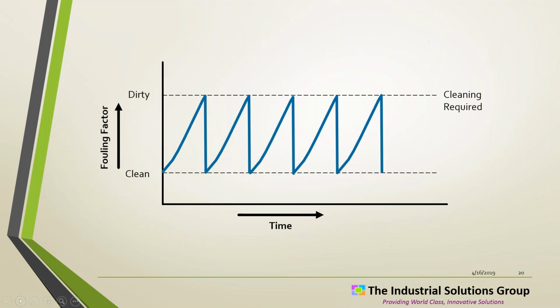I like this. I always call these shark teeth. I see them referred to sometimes as sawtooth combs, sawtooth curves. But basically, when you're dealing with heat exchangers, you deal a lot with fouling factor, which is a measure of how dirty a surface is getting. You start clean with clean tubes, and you get a certain amount of heat transfer. And then there's usually a cap. You want to go up to the dirty line.